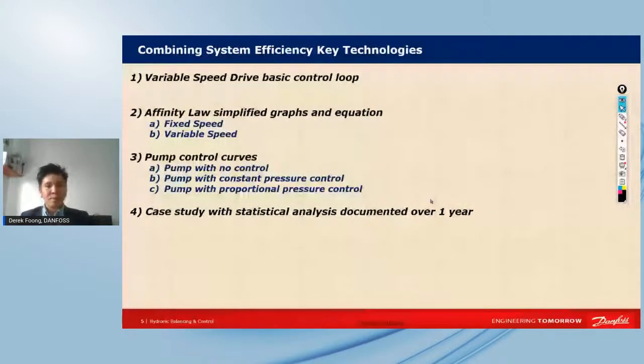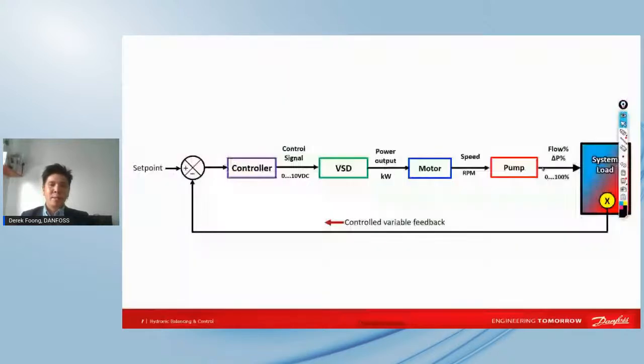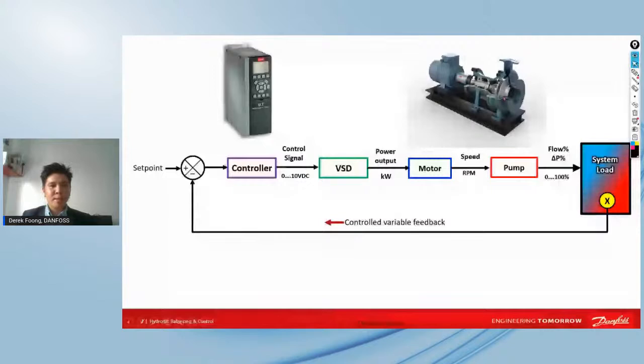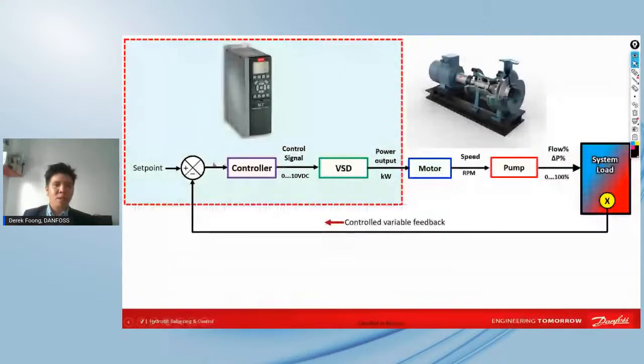So now let's go to the basic control loop. This is one of the topics that, of course, when we see in universities, is just a few block diagrams. It acts as an independent controller as well, linked to the inverter, which then also monitors the pump. If we look at the inverter, it consists of the controller, and this highlighted area is where you can adjust your set point, and it gives a 0 to 10 volts signal. Then the variable speed drive will modulate the power output to the pump motors, which is this part, and the motor will drive the pump impeller, the speed.